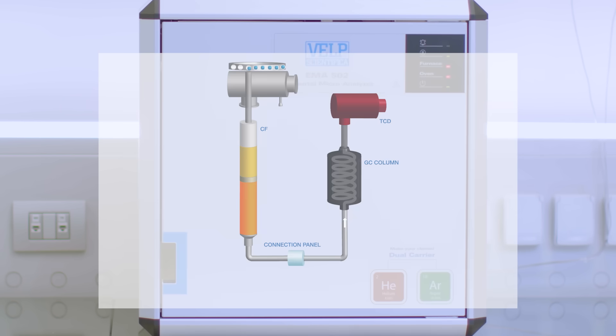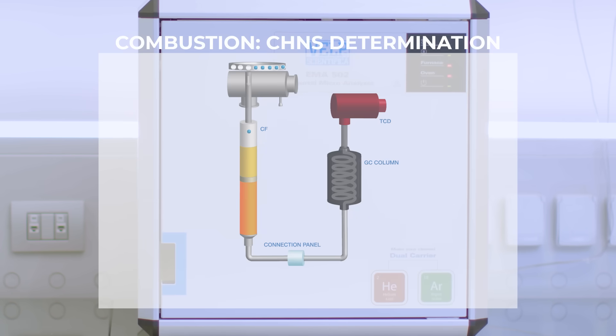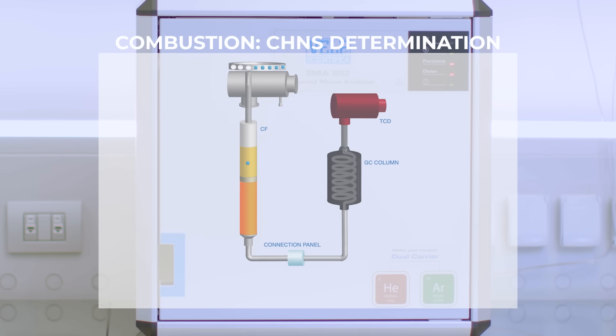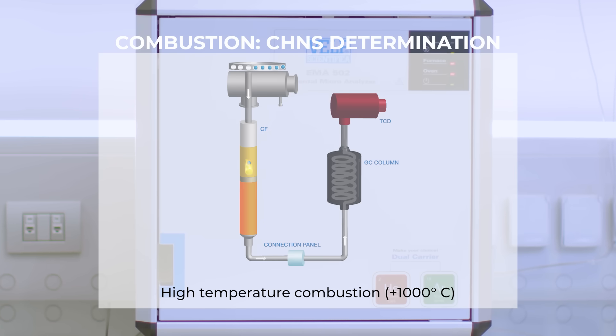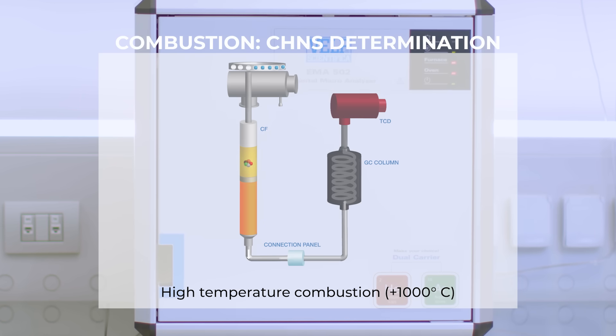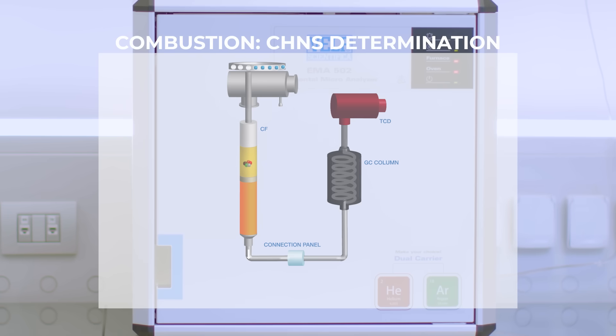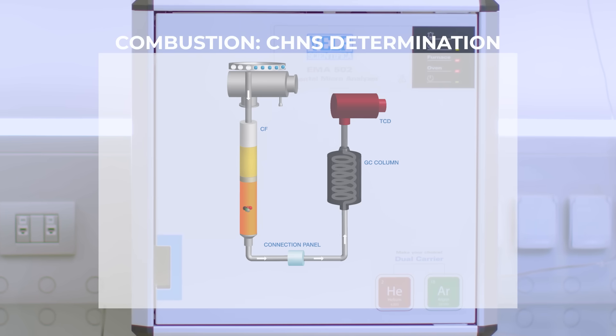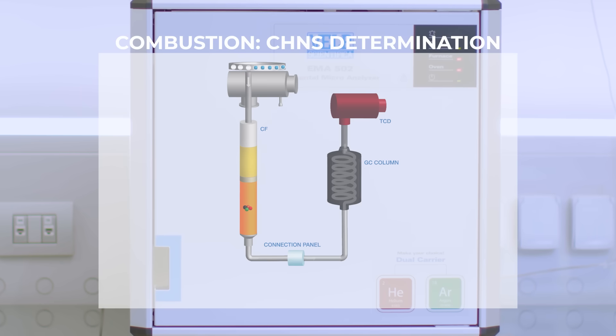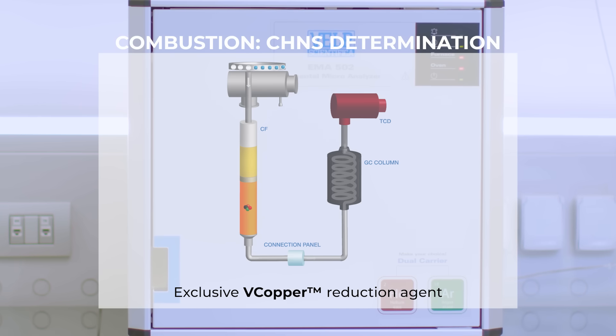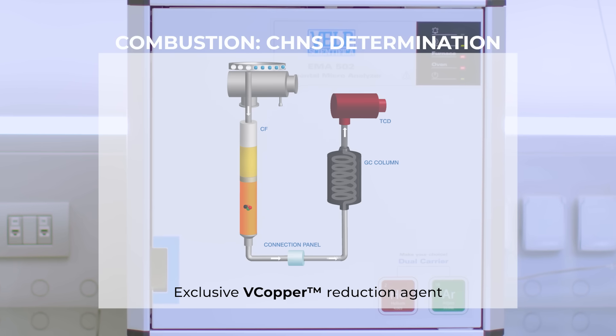The sample is purged with the carrier gas and drops down into the reactor. The CHNS analysis starts with the combustion of the sample at a temperature higher than 1000 degrees Celsius to obtain elemental compounds. During reduction, VELP V-copper reduces nitrogen dioxide to molecular nitrogen. VELP V-copper is a formulation of highly active copper powder placed in the lower part of the reactor.